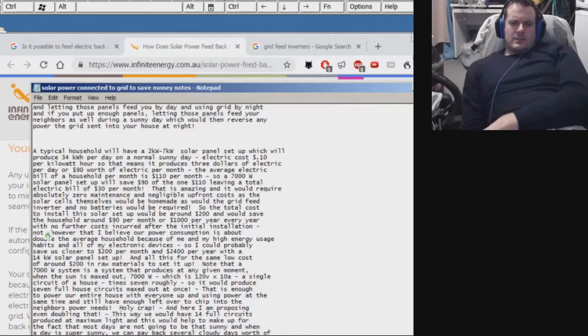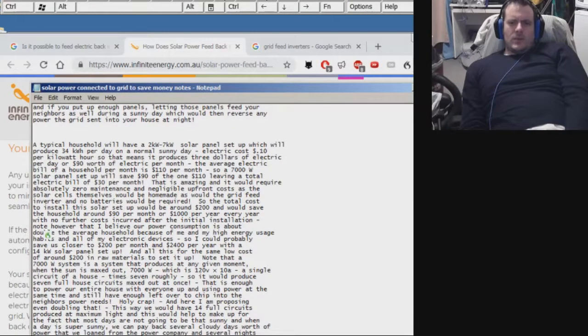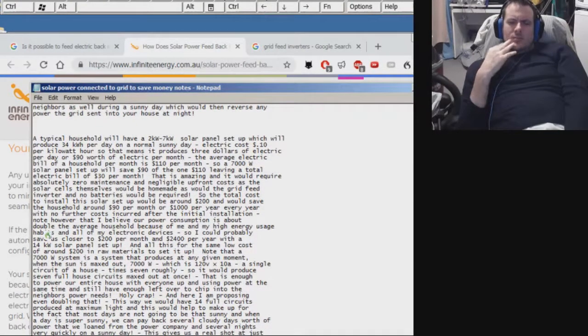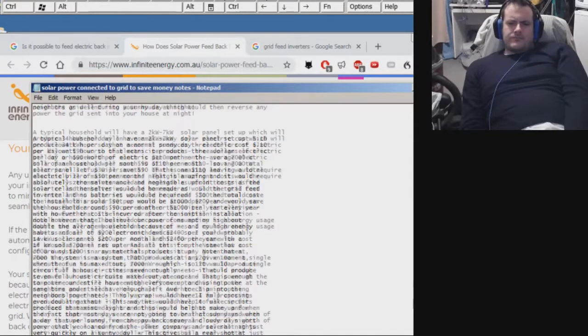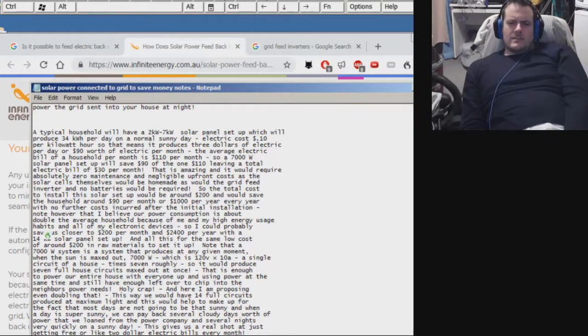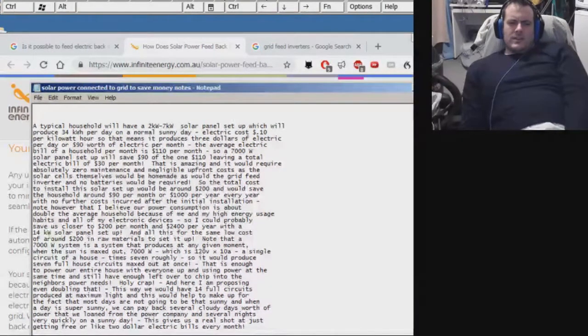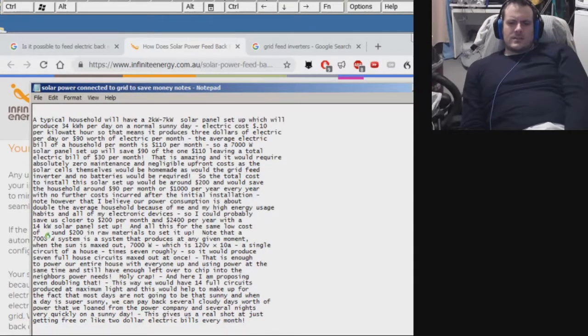Note that, unlike the example I mentioned before, it would be more practical to tie the solar systems directly at the root lines leading to our breaker box, because those don't have circuit breakers on them, and they would feed our whole house seamlessly without the need to connect to tons of lines leading to various parts of the house, and instead just tying into the trunk line.